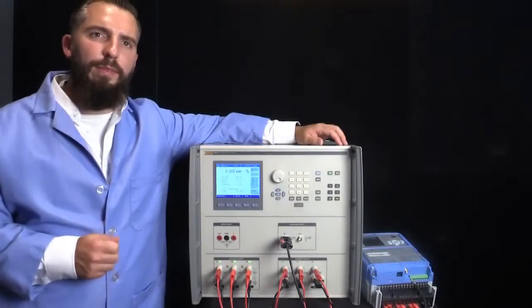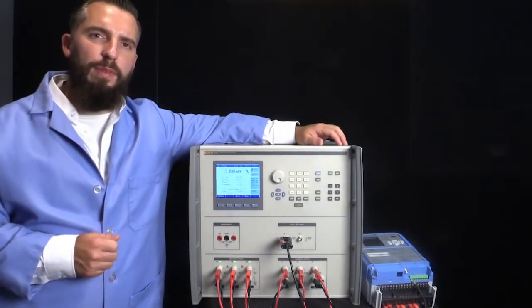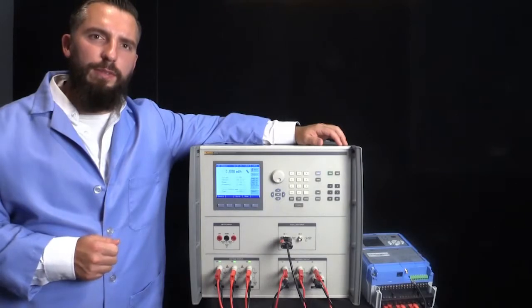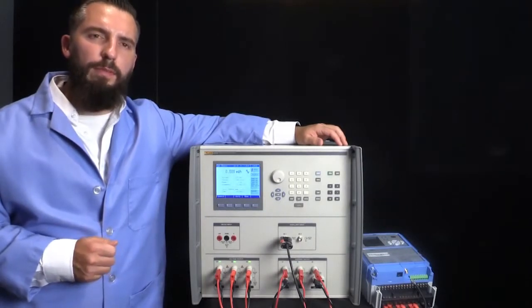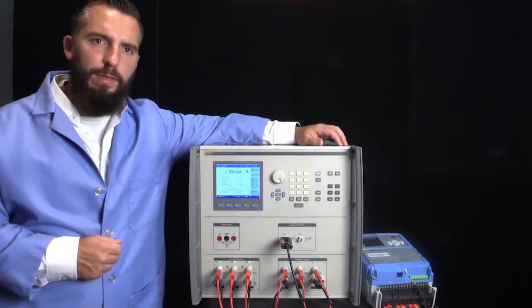In some cases, you may have to test an energy meter without a pulse output. In this case, the simplest method is to do a timed energy test where you compare the expected value to the measured value on the energy meter. This can be done using the packet mode.